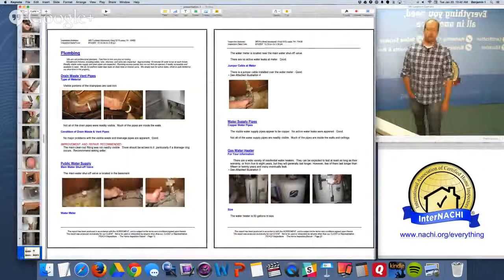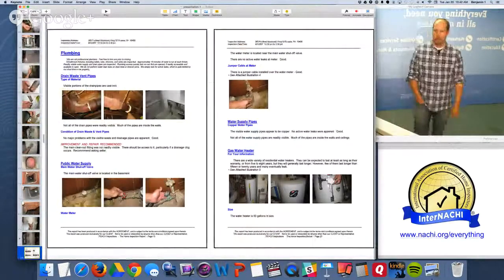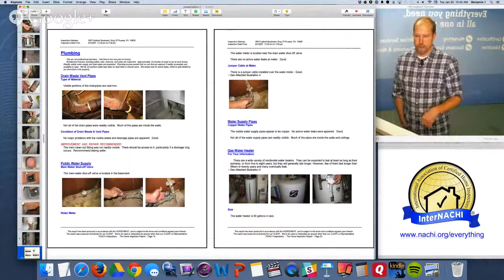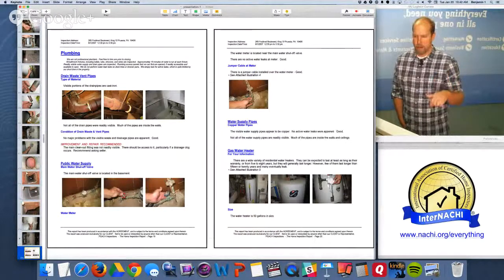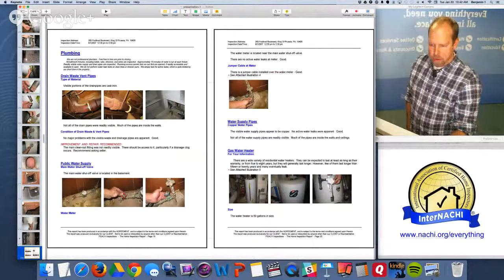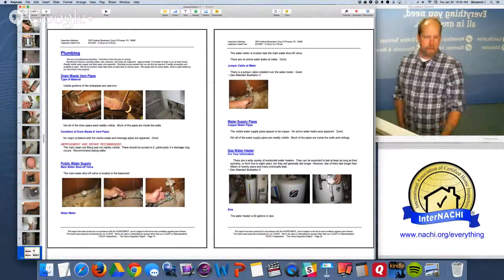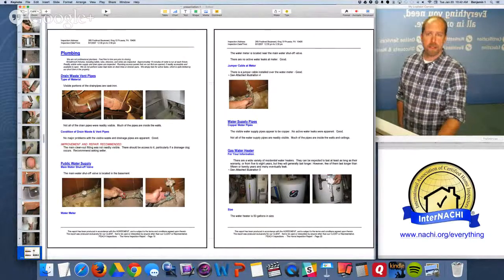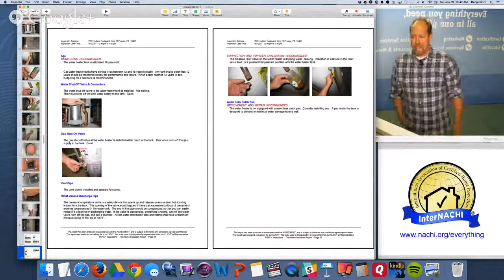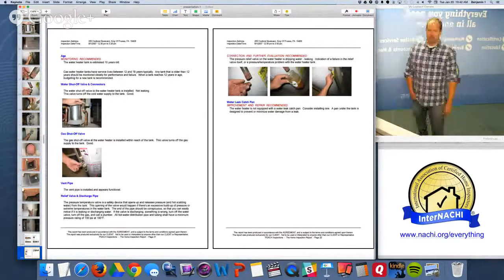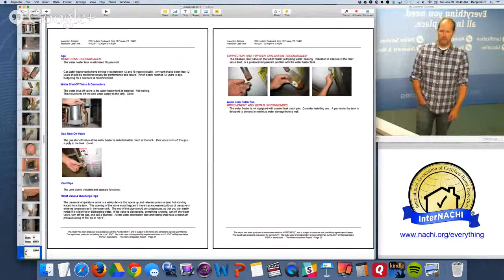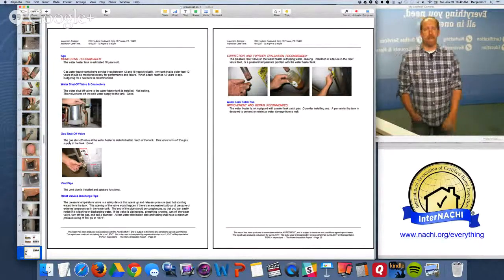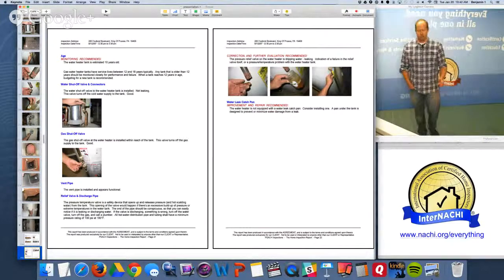The structure of the chimney is good. Here's the plumbing system report: drain waste vent pipes — type of material and condition; public water supply, water shutoff valve, water meter, jumper cable, water supply pipes description, gas water heater. I comment on the size, age, water shutoff valve, gas shutoff valve, vent pipe, and the relief valve. The discharge has no water leak catch pan — I don't like seeing a hot water tank without a catch pan underneath it, whether it's in the basement or the garage.